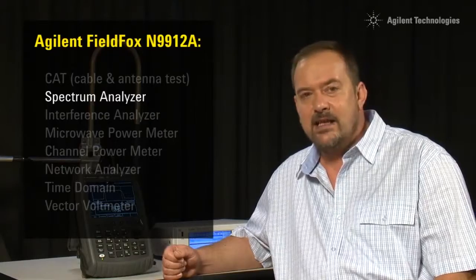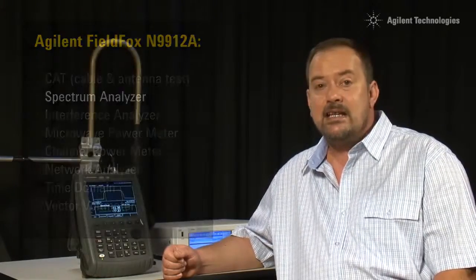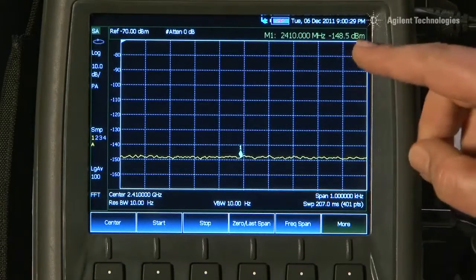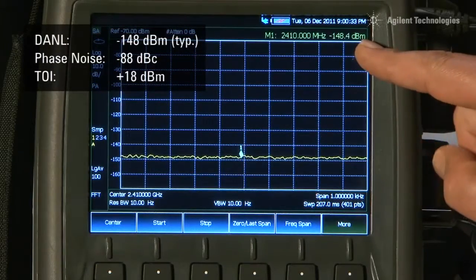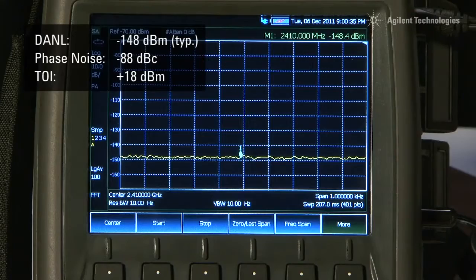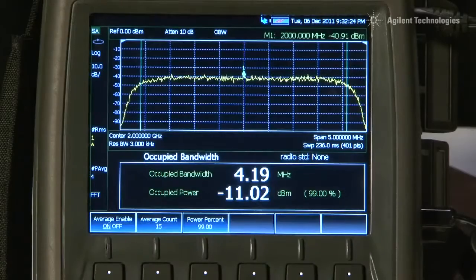The optional spectrum analyzer is quite outstanding. It can measure signals as low as minus 148 dBm, with a phase noise of only minus 88 dBc and a third order intercept better than plus 18 dBm.